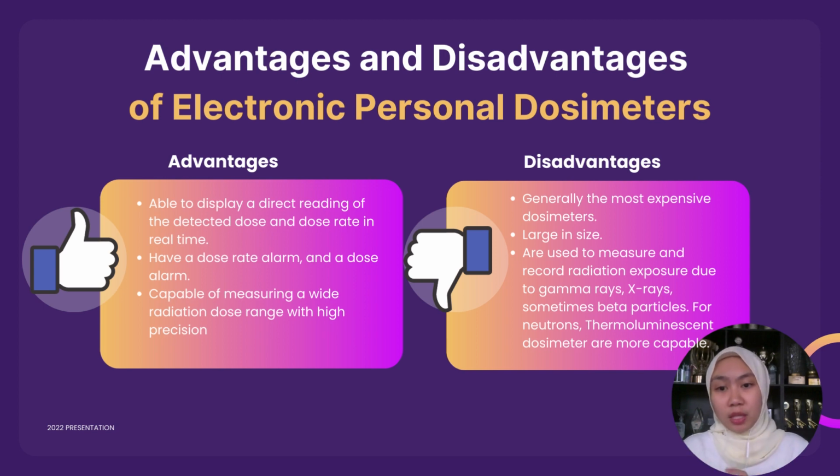Thirdly, this dosimeter is capable of measuring a wide radiation dose range, from routine microsievert levels to emergency levels of hundreds of millisieverts or units of sieverts, with high precision.